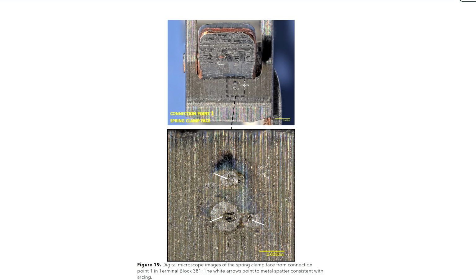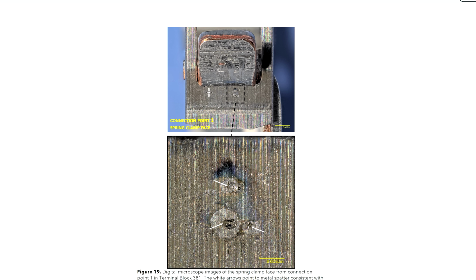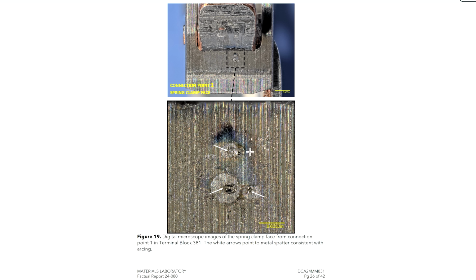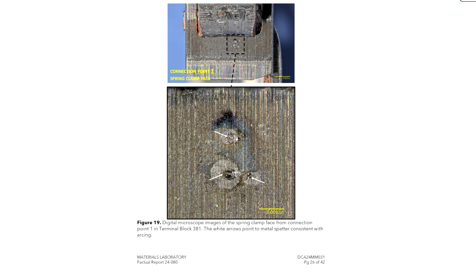Under the digital microscope, here's that top view of the clip again with the hole in it. The tool makes the whole clamp slide down so that this square hole slides down and the wire is supposed to go in it and stay pinched there. But instead, the wire popped up, the clip snapped back, and now you have arcing over the top of the clip, the spring clamp. Here's a close-up view of the arcing. Yeah, that was pretty serious stuff going on there.